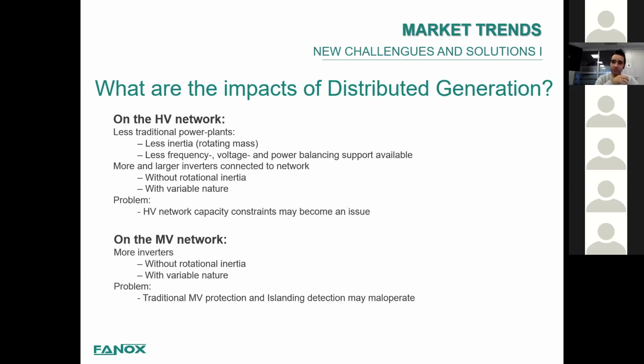as the amount of renewable energy is increasing, we are having fewer traditional power plants, which means less inertia, and less frequency, voltage, and power balancing support. And as the inverters and the wind farms are becoming bigger and bigger, we have more power supplies without rotational inertia and with a variable nature. The problem is that the HV network capacity constraints may become an issue. And if these farms are connected on the MV network, again, these inverters with less rotational inertia and with variable nature make it so that the traditional protections of the MV system and islanding detection may maloperate.